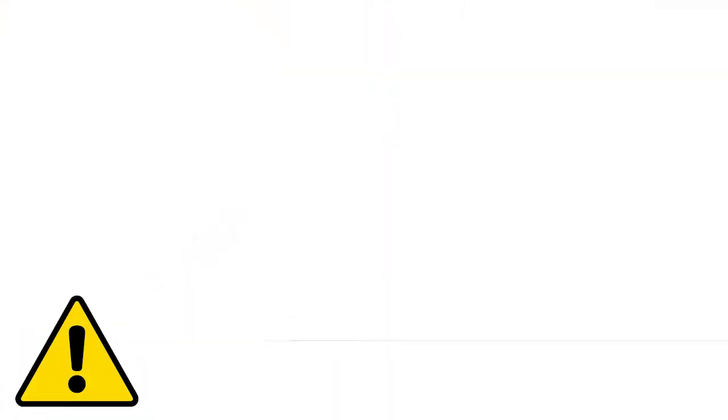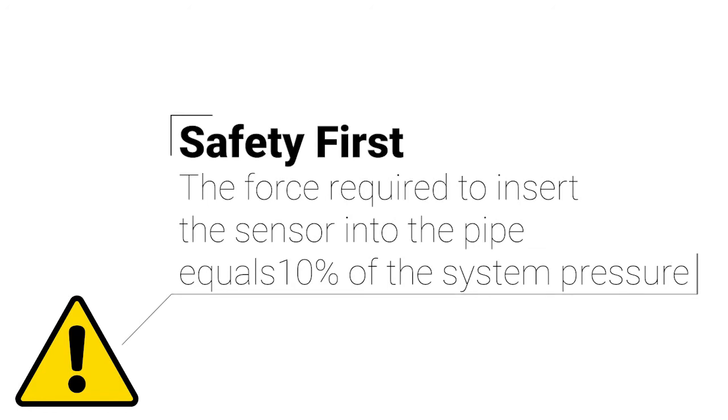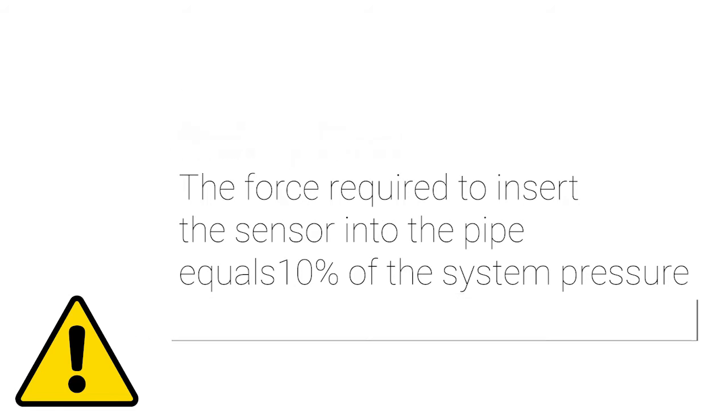Before continuing, please note that the force required to insert the sensor into the pipe is equal to 10% of the system pressure. Make sure you have adequate support before inserting the flow sensor.